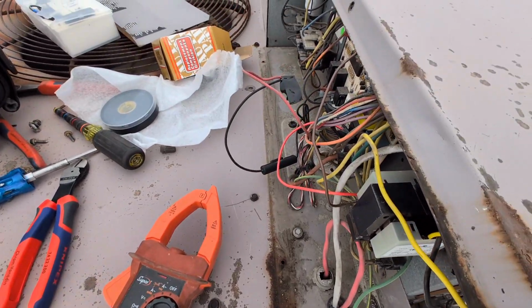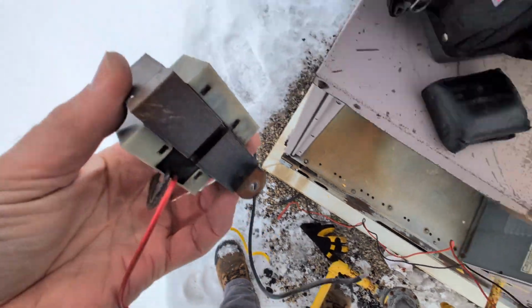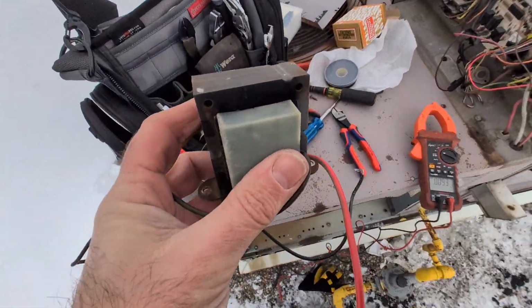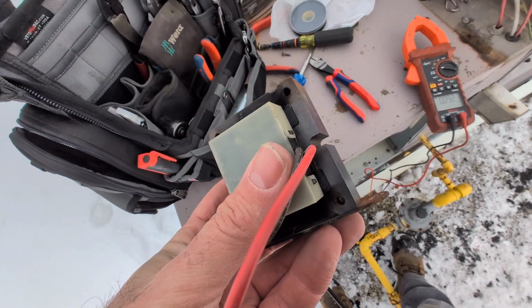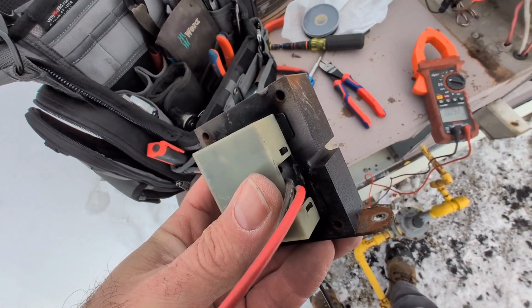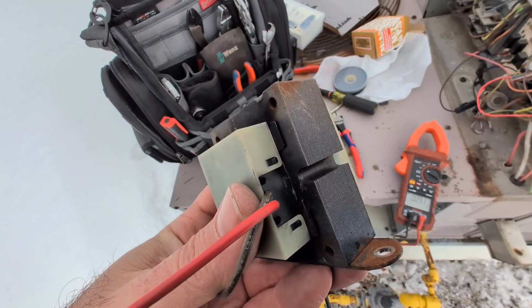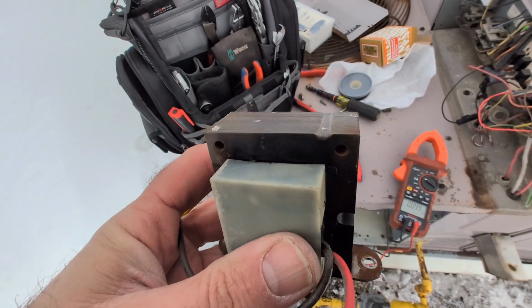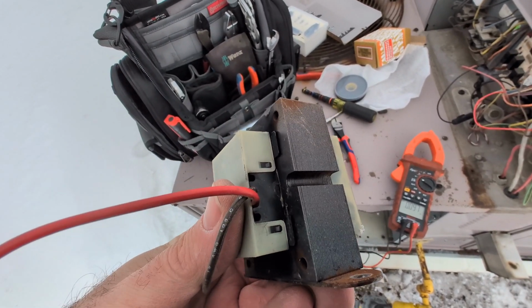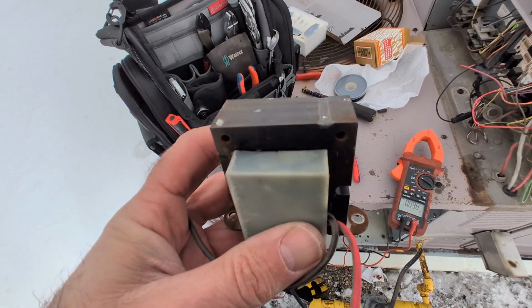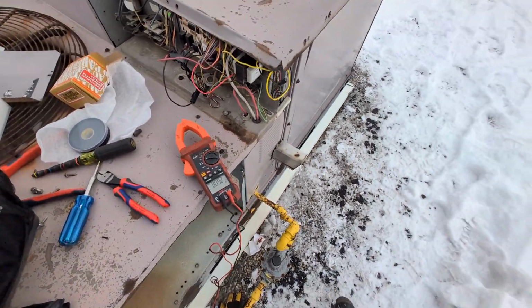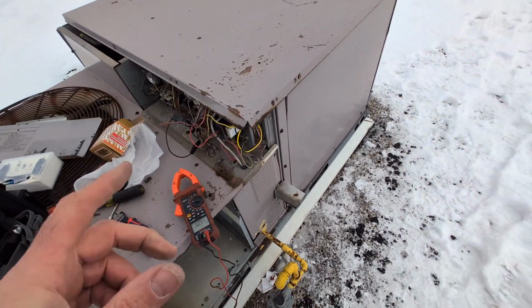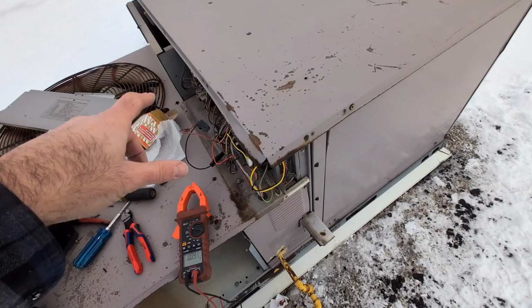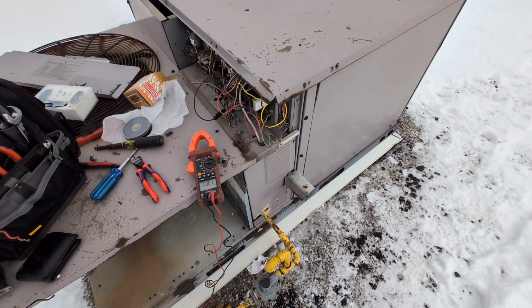The fuse has not popped, which tells me the transformer suffered some fate of, I'm going to throw it to bad weather. We had a lot of snow over the last couple of days, and my guess is it got wet and shorted, and that's the cause of it. So anyway, we're back up and running now. I'll go check the thermostat, put some correct wire connections on here, and clean up. We're done. Happy HVAC.